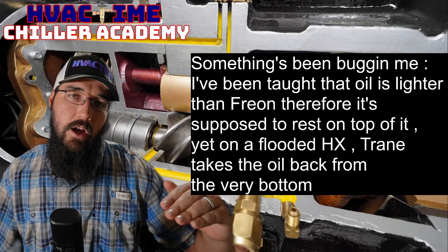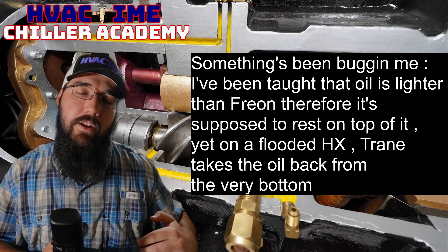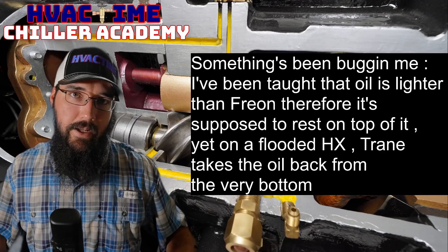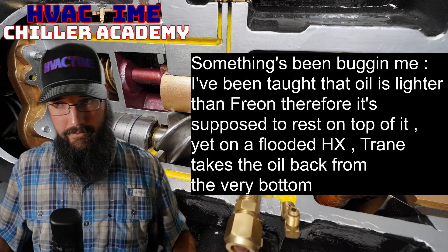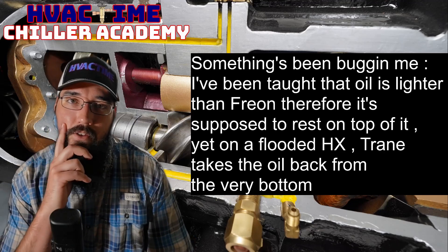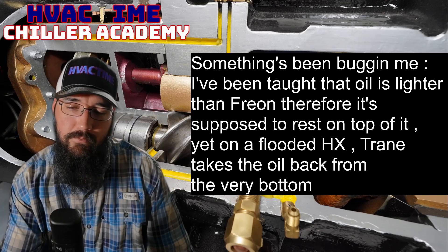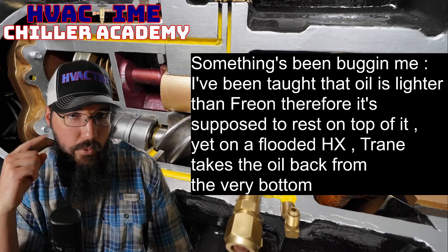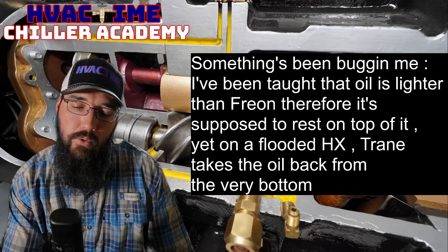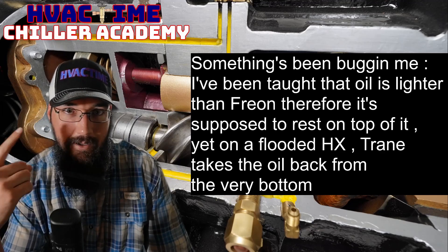So yes, it is still true that oil sits on top of refrigerant — but because of the evaporator design, it makes sense to pull off the bottom of a falling film evaporator because that's where the oil-laden refrigerant is. Without diving deep into this, it can be tricky to process intuitively. I remember looking at this and thinking it just didn't add up — my intuition said oil should be on the bottom, but it doesn't.